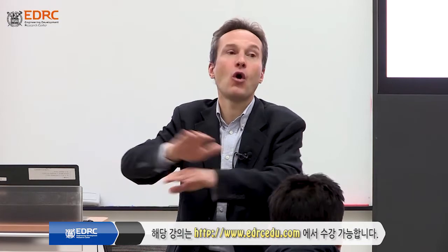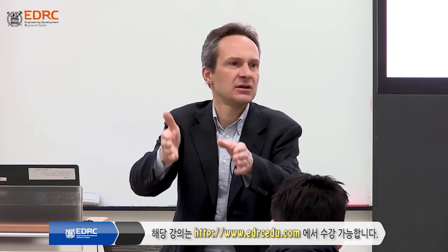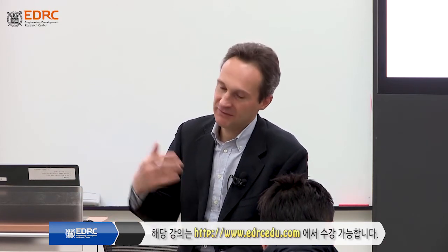So this information, MDMT, will be specified on the datasheet of each equipment. Why? Because it could be different for each one. As a rule, it will be the same for all, except those containing products that can bring the temperature very low during depressurization - or high-pressure gas. When you have high-pressure gas systems, you'll find the vessel will be in low-temperature carbon steel because of the depressurization, not because of normal operating temperature or site condition.